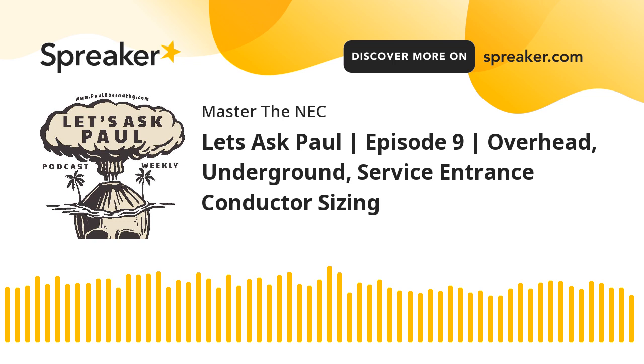Now, it goes on a little further. It says, conductors shall be sized not less than the larger or the largest of 230.42 A1 or A2. Now it says load shall be determined in accordance with part 3, part 4, and part 5 of Article 220. Now we've rehashed this. We know that the same concepts apply here. But it's so important to know when you're dealing with service entrance conductors versus overhead or underground service conductors. We're dealing with service entrance conductors. Again, go read the definition. And so we have to size it based on the larger of A1 versus A2 of 230.42.